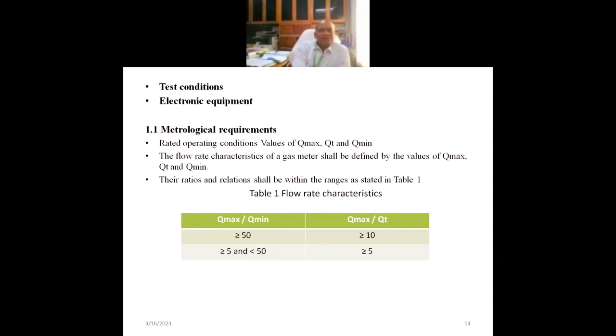And test condition, the metrological requirements, rated operating conditions, values of Q max and QT and Q minimum. The manufacturer of the gas meter should mention the rated operating conditions. The flow rate characteristics of a gas meter shall be defined by the values of Q maximum, QT and Q minimum. And these ratios and relations shall be within the ranges as stated in Table 1. If the Q maximum divided by Q minimum ratio is greater than 50, then the Q maximum and QT ratio should be greater than or equal to 10. And whenever the Q maximum and Q minimum ratio is greater than 5 and less than 50, the Q maximum and QT ratio should be greater than or equal to 5.